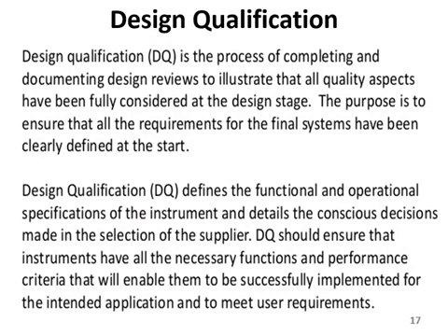Design qualification, DQ, is a process of completing and documenting design reviews to illustrate that all quality aspects have been fully considered at the design stage. While you are designing the process, right? You have considered all the possible things which you are going to see or face during the process. The purpose is to ensure that all the requirements for the final system have been clearly defined at the start. At the start, you must be defining each and everything.